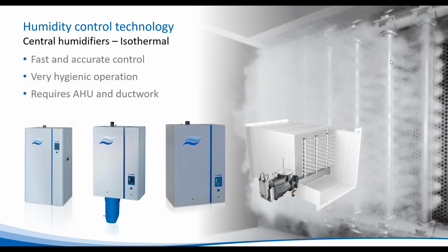So the absorption distance is a critical factor when we put steam into the duct, because there is a distance, or a section length, required that will allow the steam to be mixed with the air before any point where condensation could occur. So you get very fast, accurate control with these types of systems. It's very hygienic because we're using steam, but you do require an air handling unit or ductwork. And typically we're using electricity to produce steam.